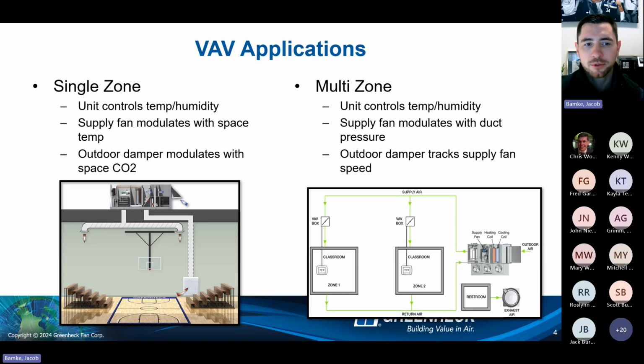So whatever space CO2 we're trying to maintain, dampers would automatically open or close based off of how much CO2 is built up in that space. When you get to the multi-zone VAV situation, now you still have a single unit. It's still controlling both the temp and the humidity, but then you have VAV boxes downstream that are allowing more or less air to get into those classrooms.